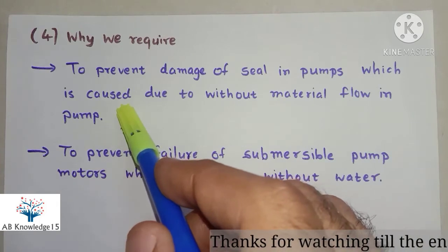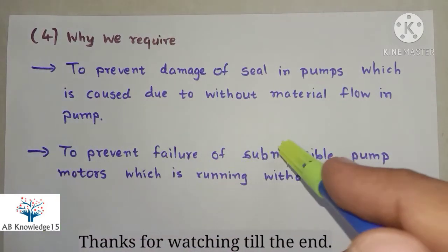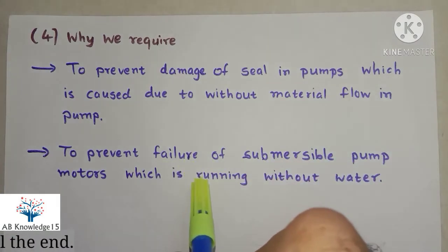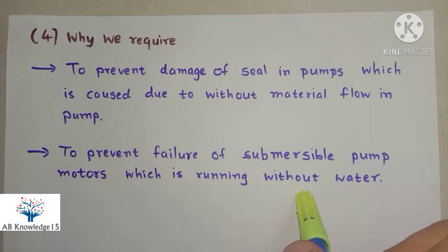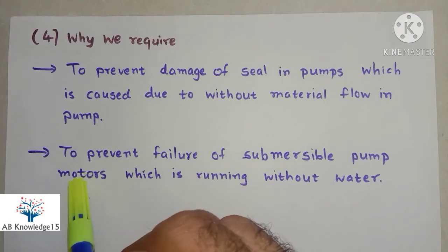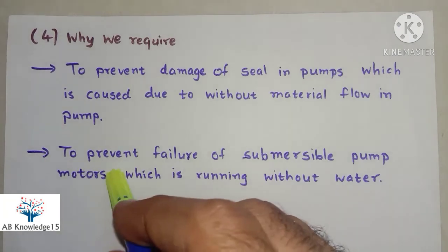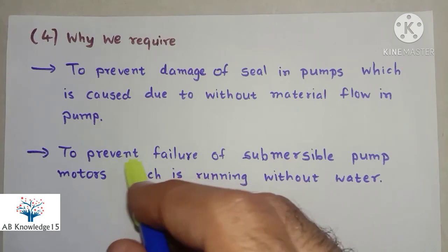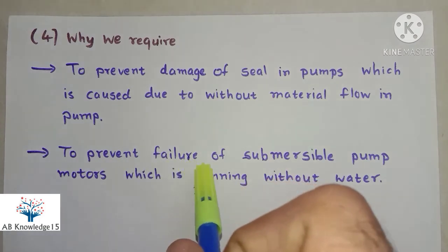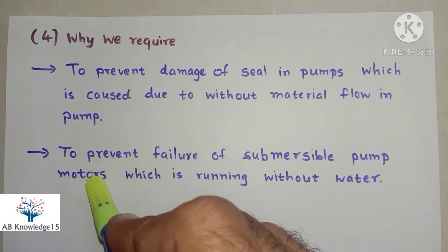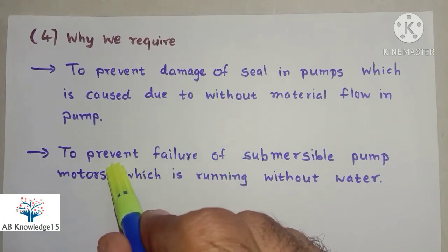And the second case is that in submersible pump motors, if the motors are running without water, then it will cause the generation of heat in the motors. The winding of the motors will not get cooled down. So in this situation, the motors may get damaged, the motors may get burned. So to prevent the failure of submersible pump motors, we require to provide them the underload protection.